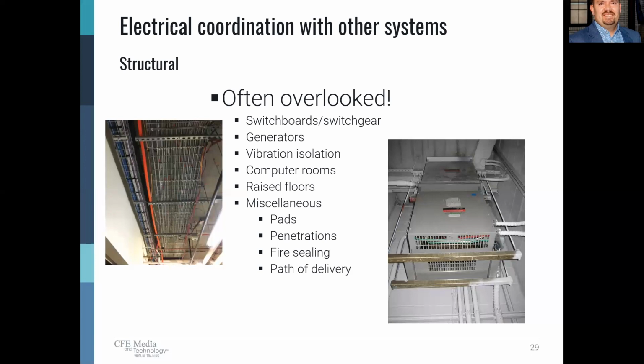Other pieces that need to be coordinated include electrical rooms, raised floors, and then there are also the miscellaneous pieces associated with our installations, like equipment pads, penetrations through structural members, the fire sealing of those penetrations, and also the path of delivery. If you take into account conduits, oftentimes a conduit rack passes from one end of a building to the other with multiple conduits. The amount of weight that introduces to the building is often overlooked. We need to make sure that we have that accommodated in the structural design.